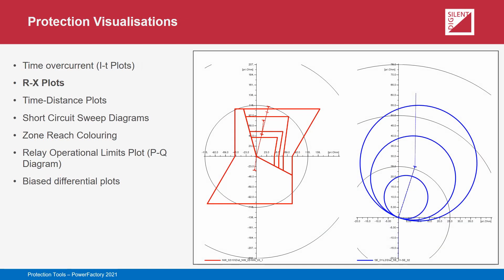RX plots are used with distance protection, representing the tripping characteristics of distance relays on a resistance versus reactance plane. The impedances of the protected lines and equipment can be shown on the same diagram. When calculations or simulations are carried out, the line-to-line and line-to-ground fault loops calculated by the relay's polarizing blocks can be illustrated and compared to the tripping characteristics. For simulations, it is possible to plot the impedance trajectory that occurs during a disturbance, which is particularly useful for examining power swings and out-of-step and power-swing blocking relays.